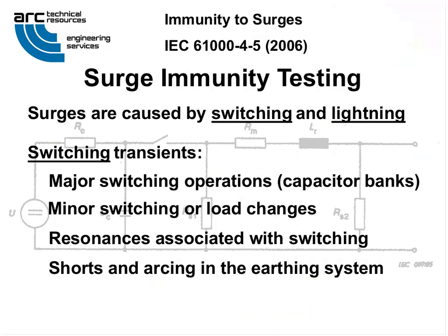61000-4-5 surge immunity testing. Unidirectional overvoltages or surges are caused by switching or by lightning transients. Switching transients are associated with major power system switching operations like cap bank switching, minor switching operations near instrumentation or load changes out in distribution can cause them, resonance circuits used with switching devices like thyristors, or short circuit or arcing faults in the earthing system of the installation.